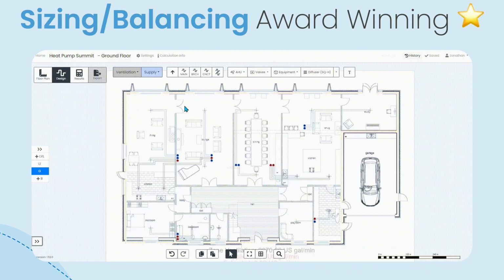Whereas taking a look at the software now, this is moving pretty fast, but what's happening here is they're distributing the flow rate equally. They're actually drawing out the system of what they plan to install. This is a supply and extract. Because they've done the load calcs, the flow rate is coming into the diffusers and the grills. And what's really important is, although it's sizing the fan to get to the most disadvantaged part of the system, it is making sure all the pressures are equal.